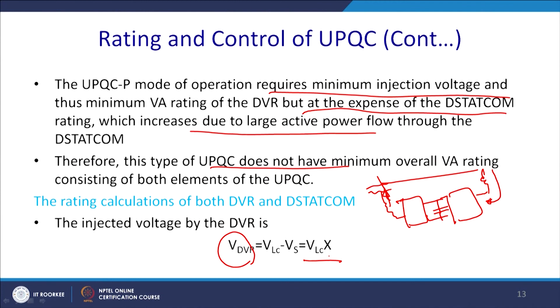And for the rating calculation of the DVR and the STATCOM, the DVR rating will be VL minus VS, that is VL into X. You have to design for how much sag occurs at that particular place, 40% sag, 30% sag or something like that, or in the same way the swell. So generally you have over voltage and under voltage relays, and accordingly you have to take care and calculate the value of X. The VA rating of the DVR is totally an active power and is expressed as S DVR equal to V DVR into IS. From there X VL IL cos phi will come, where IS and IL are the supply and load currents respectively, and phi is the load power factor. Here delta will not come.